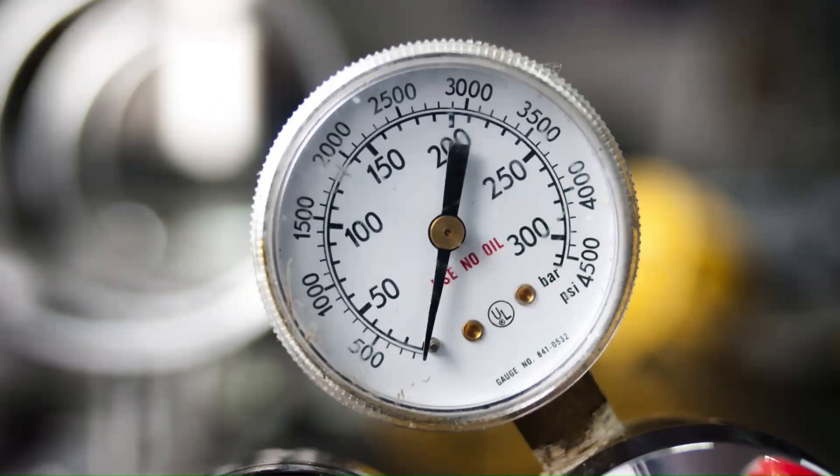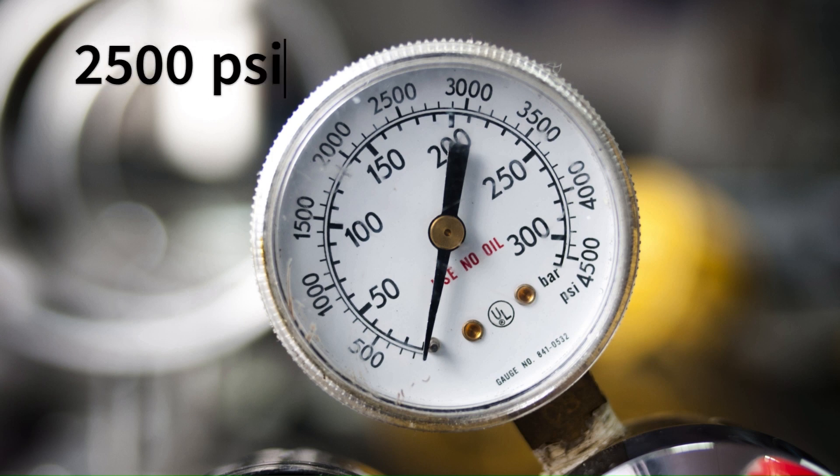The last thing we need to know is the maximum system pressure. This is determined by how much pressure the pump can generate. However, most systems will have a relief valve in place to protect from overpressurizing. So in this example, let's assume our relief valve is set to 2500 psi.